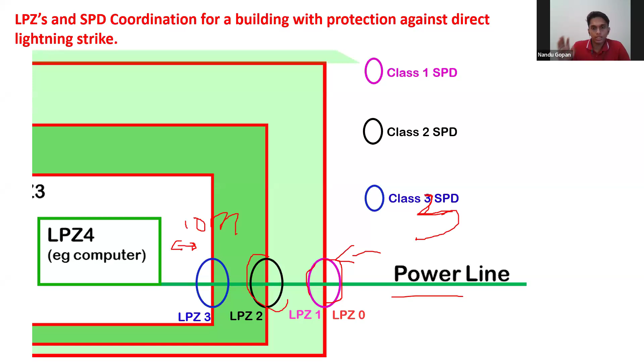This is a picture. In this picture, you have a building. When a power line is entering the building, if you want protection against a direct strike, you put an SPD class 1 here, an SPD class 2 here, and if you want, you can put an SPD class 3 here, or you can also put class 2. It depends on you. If it is sensitive equipment, then you can put class 3. And the distance between these SPDs should be less than 10 meters. That is important. So this is how it looks in a schematic representation.